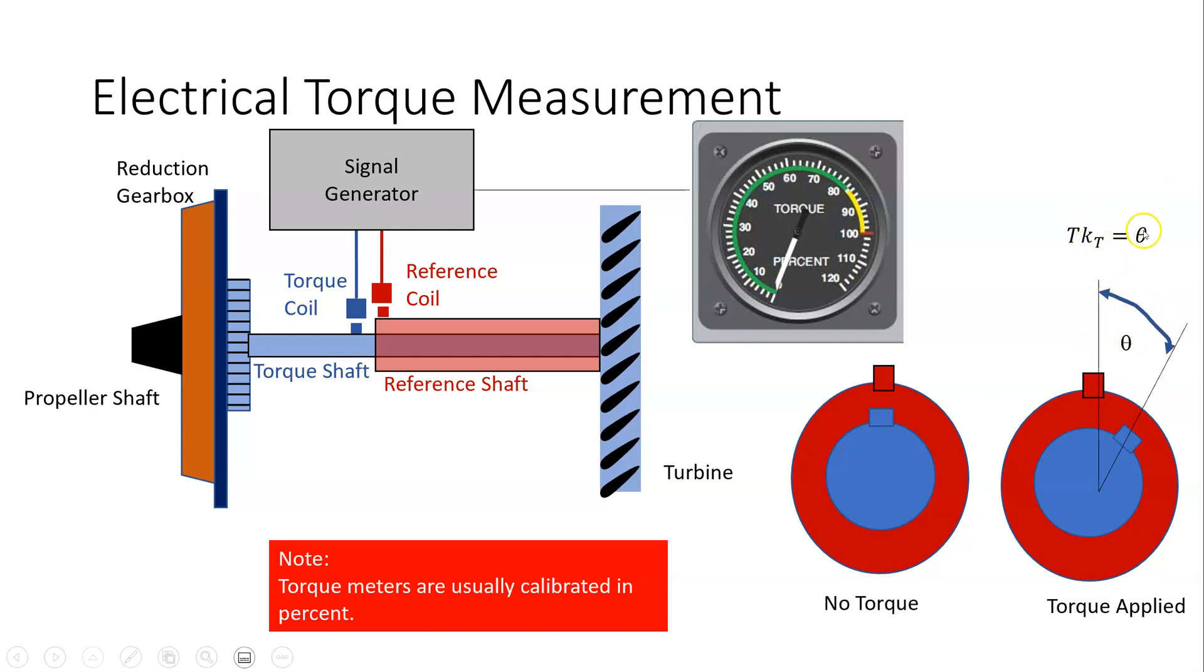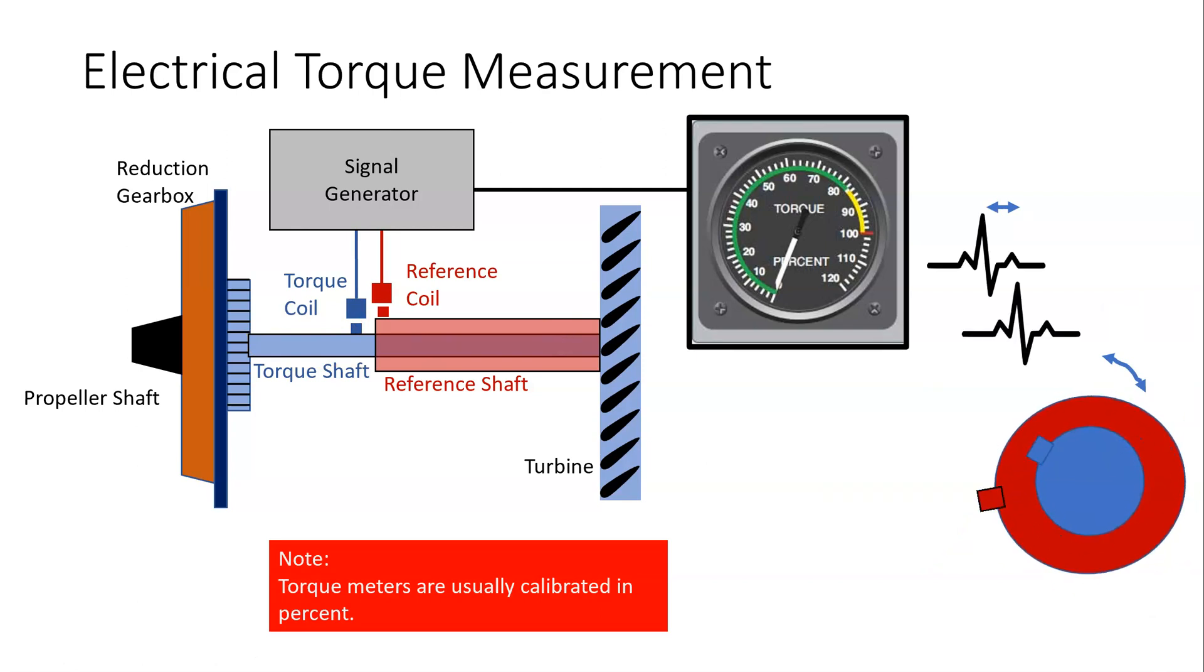So the shafts are out of phase, if you like, so there's this angle of twist between this part and this part due to this torque reaction. So when the shafts rotate, they're inducing a voltage in the coils and the signal generator here is looking at the phase angle between the induced voltages. So it's looking at the phase angle between the reference coil and the torque coil. And that phase angle theta will be equal to the angle of twist theta here.